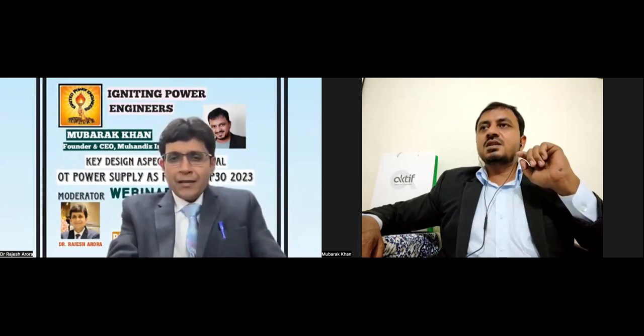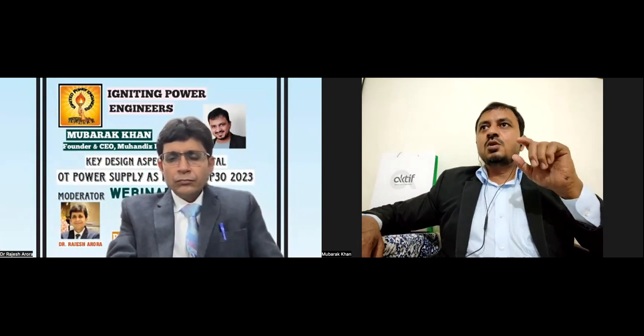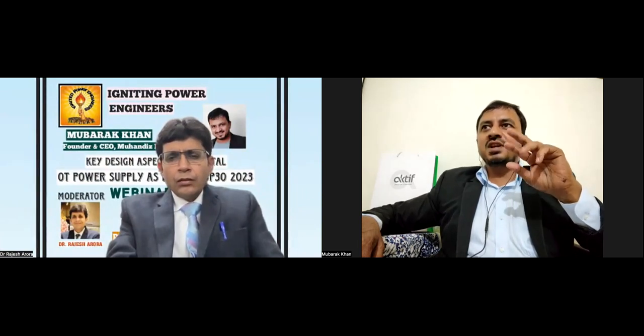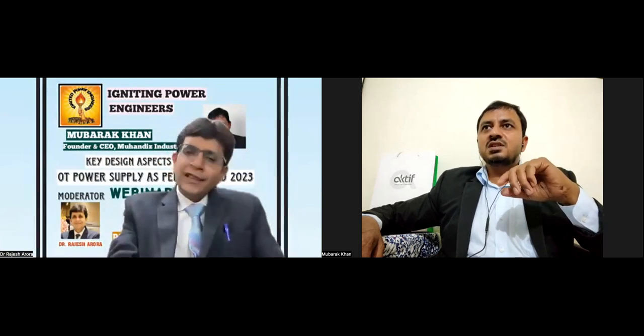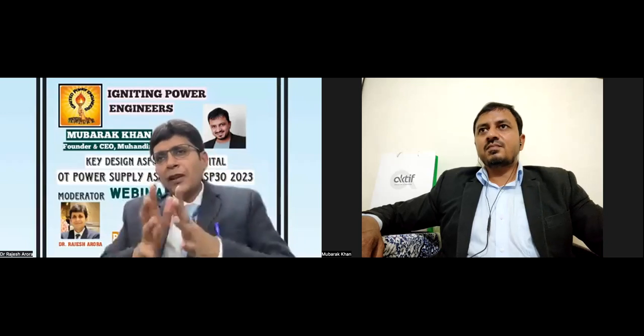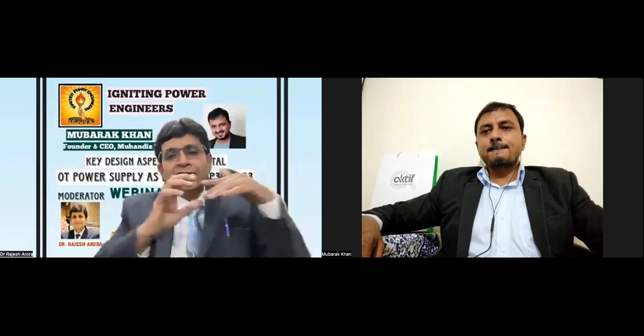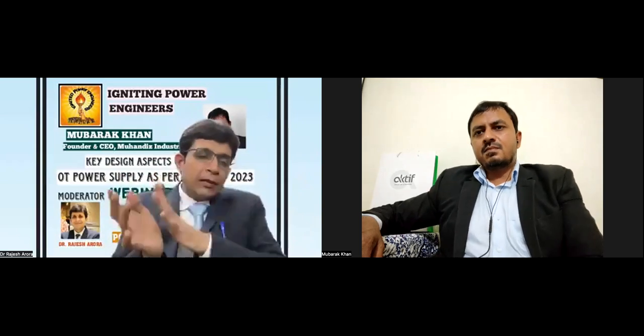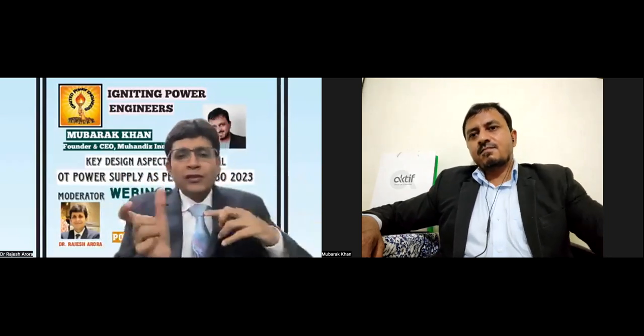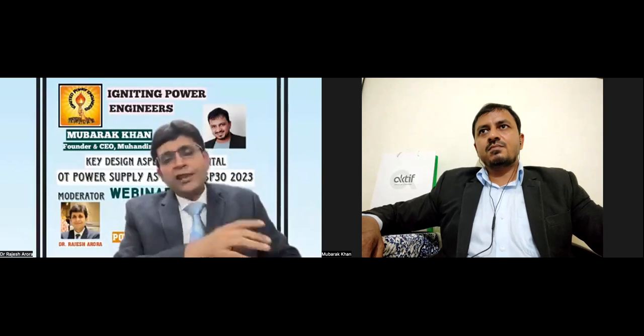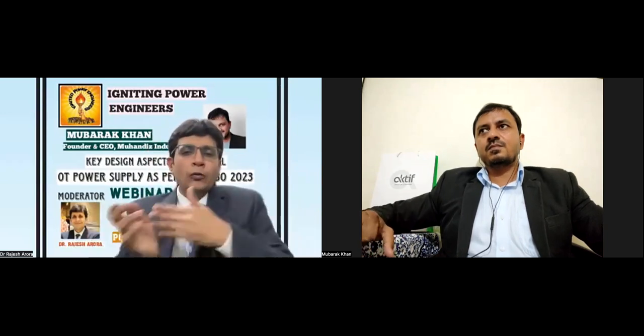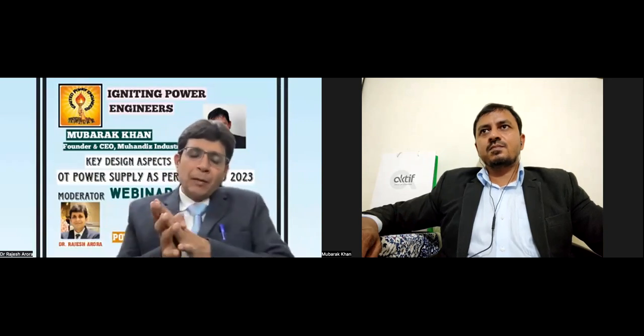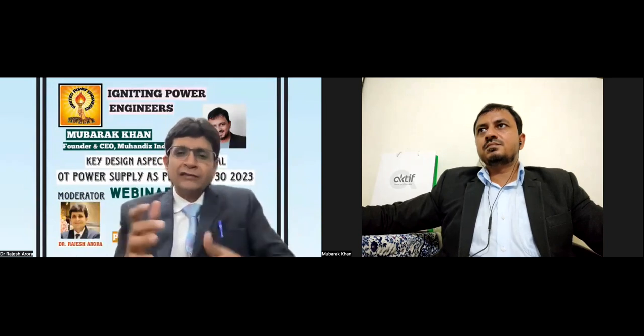Sir, when you use the isolation transformer, both the phases are 110 volts, hypothetically speaking, with respect to ground. Yes. That is the only purpose of the isolation transformer. One side is delta, the other side is star, and both are the same rating, so there is no difference. If the primary is, let's say, 10 volts, the secondary will be the same voltage. There is no step down or step up. The purpose is to keep the incomer separated from the outgoing system, the secondary system. That is the purpose of the isolation transformer in an IT system.